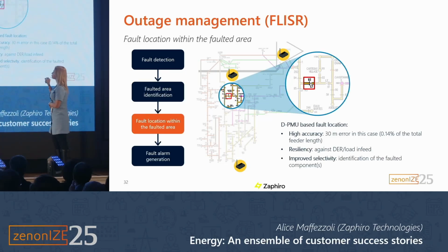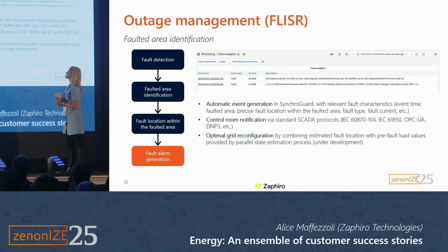And then the second step is the fault location. So basically, not only do we tell the operator between which PMUs, but we also say how far it is. We always say approximately plus or minus 100 meters, but in reality, in this case, it was, for example, a 30 meter error. And then there is the fault alarm generation. The alarm can be sent by SMS, by email, in our dashboard, but this is where the core of the presentation comes in: also integrated with the SCADA system. So the SCADA system gets an alarm, and the operator can easily see between which PMUs. The first thing that can be done is to restore the healthy part of the grid, focus on the part where the fault is, and then send the team to check approximately, as we said, 30 meters from the PMU where the fault is.